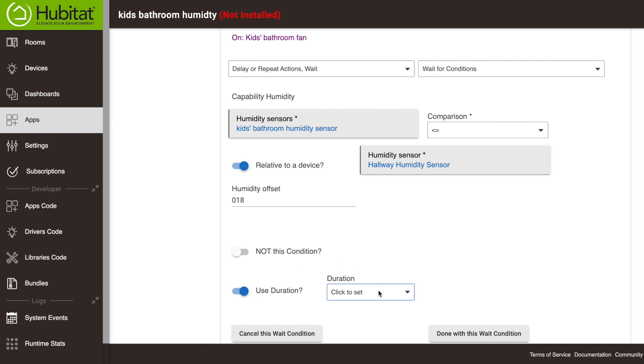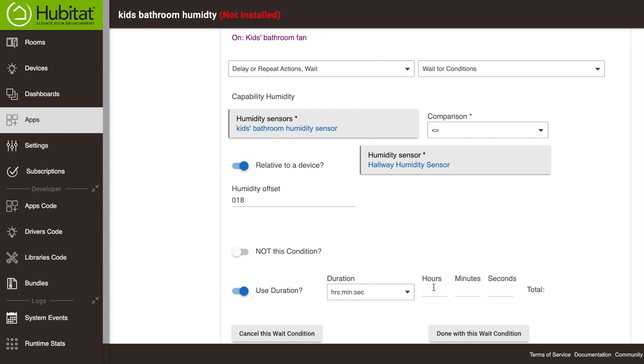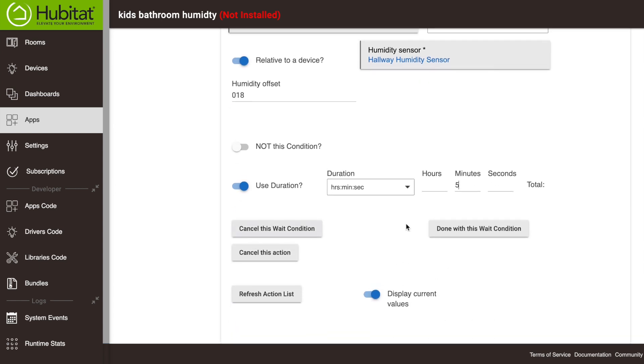So we're saying we're going to select a time of five minutes. So we're going to say when these conditions have been met for five minutes, when this humidity has been 18 or lower compared to the hallway humidity sensor for five minutes, then it's going to trigger our next action. So we're going to be done with this wait condition right here. And you can see we're going to be done with the wait condition.